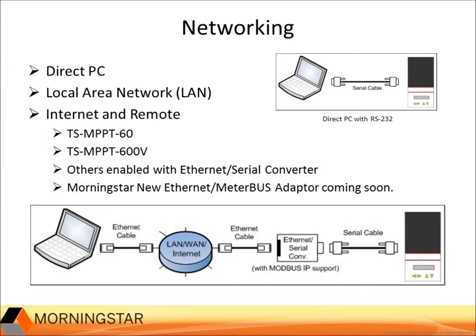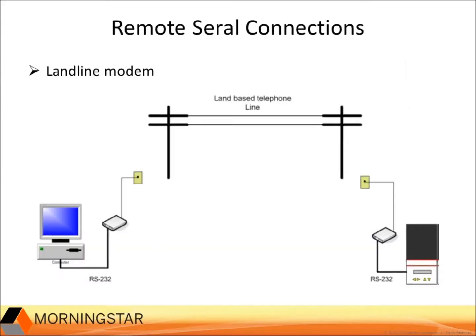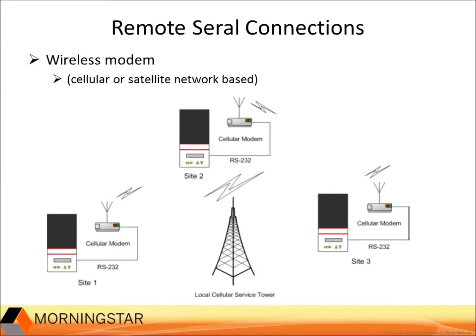It is only possible to connect to the internet using an Ethernet TCP/IP interface. Remote serial connections are possible, but they are basically direct serial connections rather than routed internet connections. Here is an example of a remote serial connection using a landline. It is also possible to use cellular or satellite wireless communications for remote serial communications.